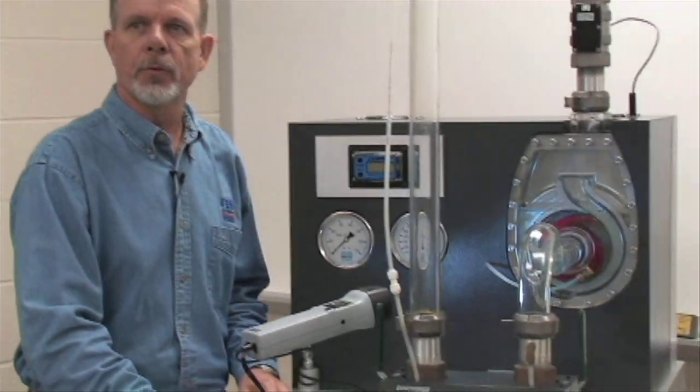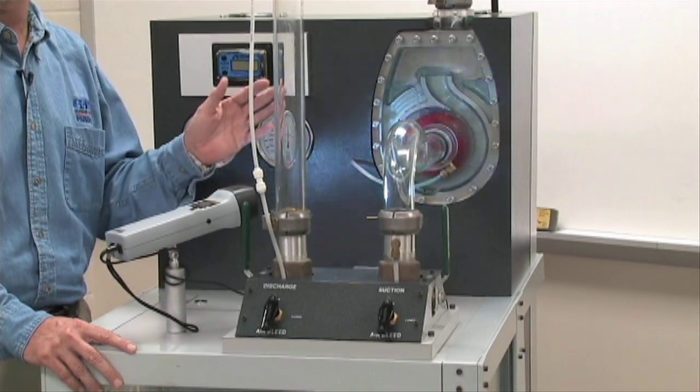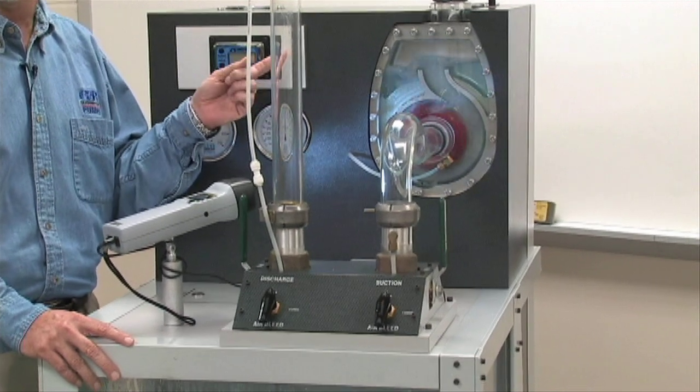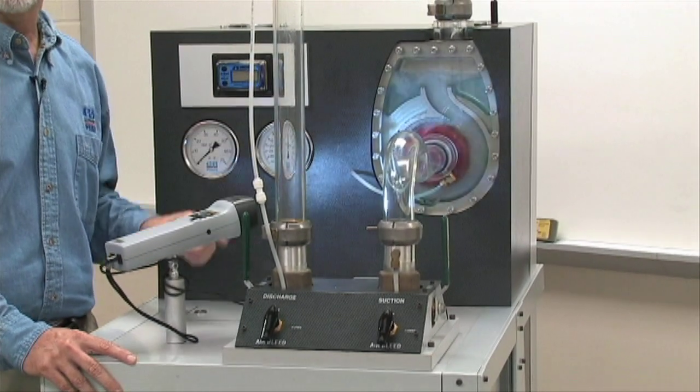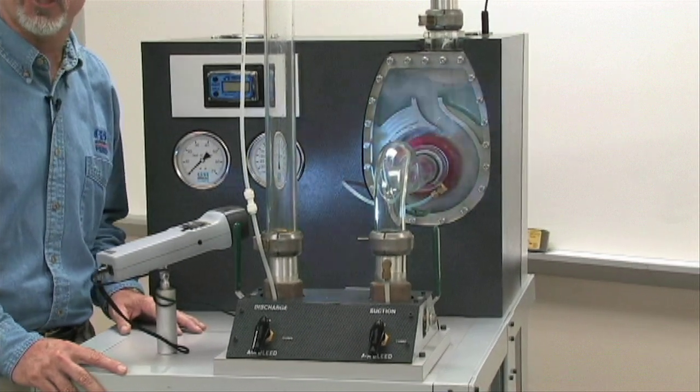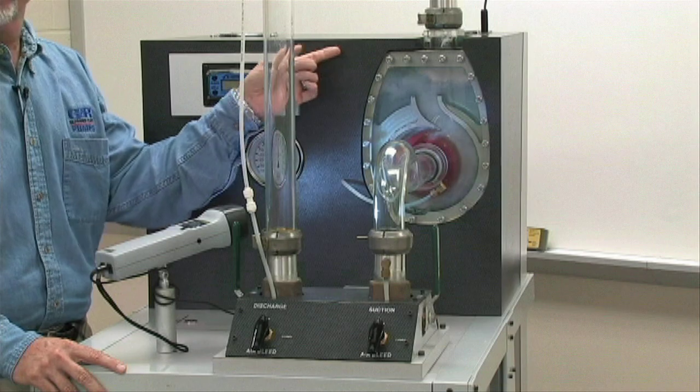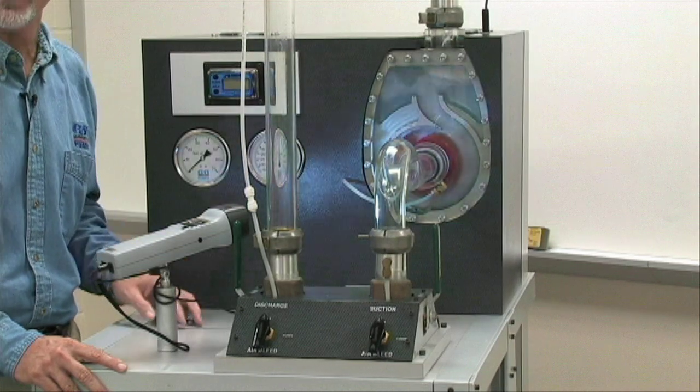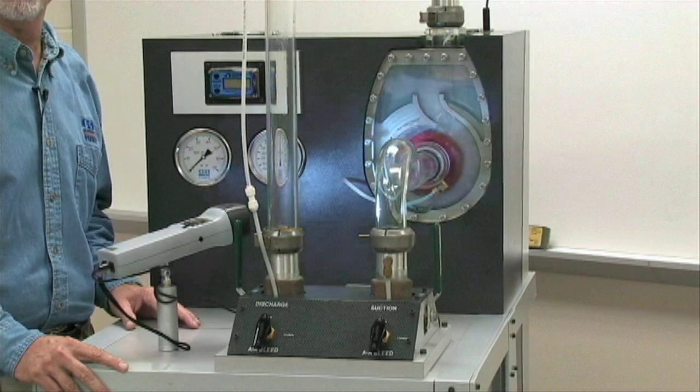Another cause of failure to prime is air binding. During priming, air is handled through the recirculation process and evacuated off the discharge side. Air binding occurs when air is not vented to the atmosphere and collects on the discharge side. The now pressurized discharge line stalls the priming process until the air can be vented.